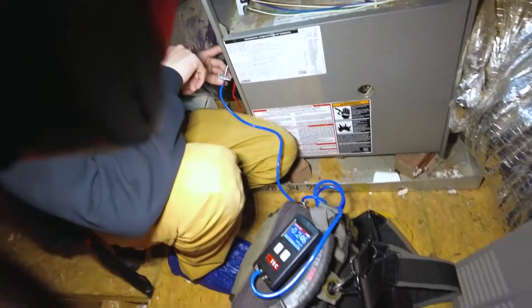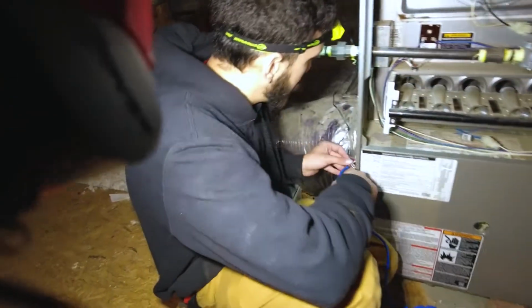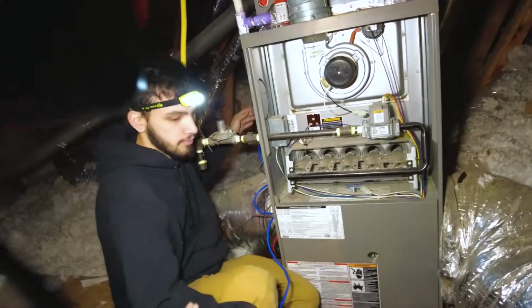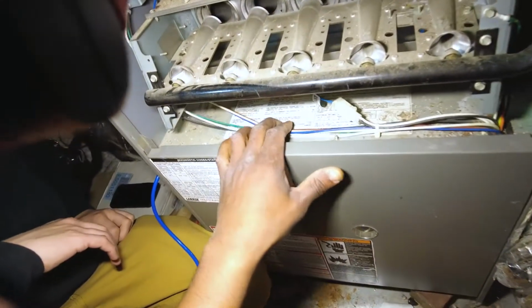As we see, we've got 0.24. You can keep that there for a sec. Now we'll do supply, you can pull that out real quick please, and then pop in. Is that good or bad? It's actually decent. You want a total of no more than 0.5, which is what's on the data plate of this furnace. You can actually read it here.